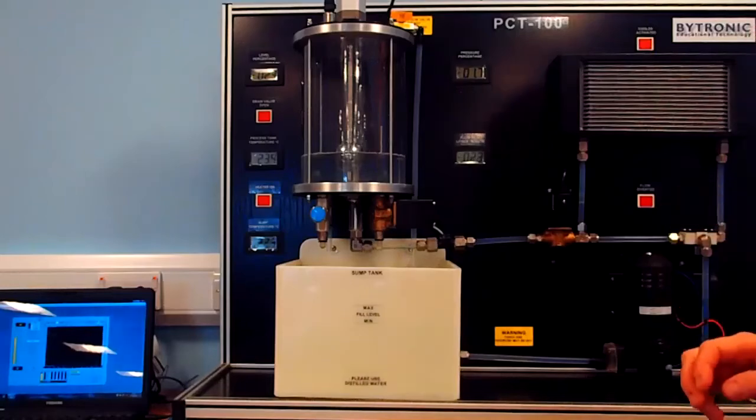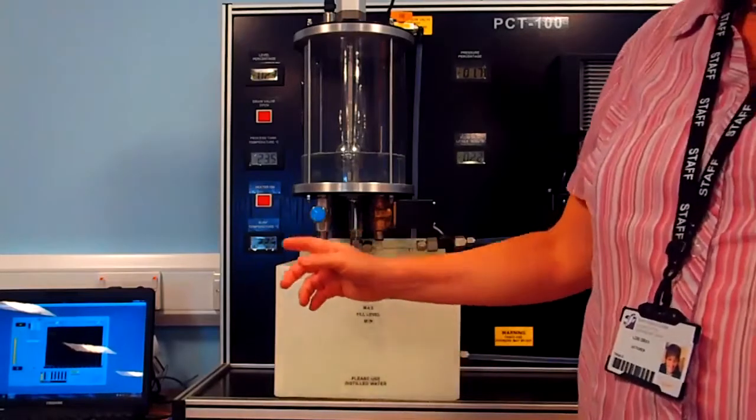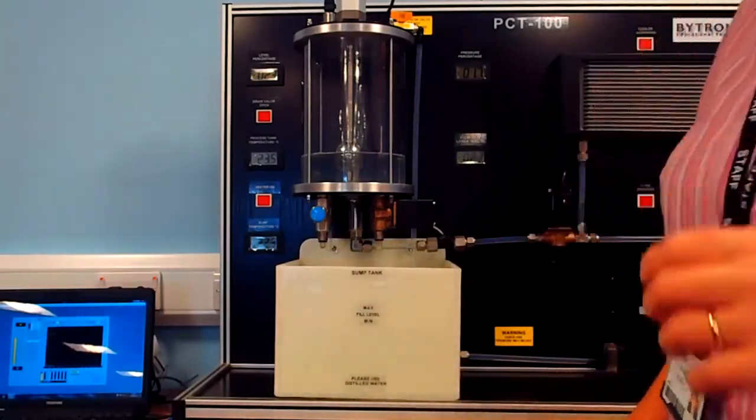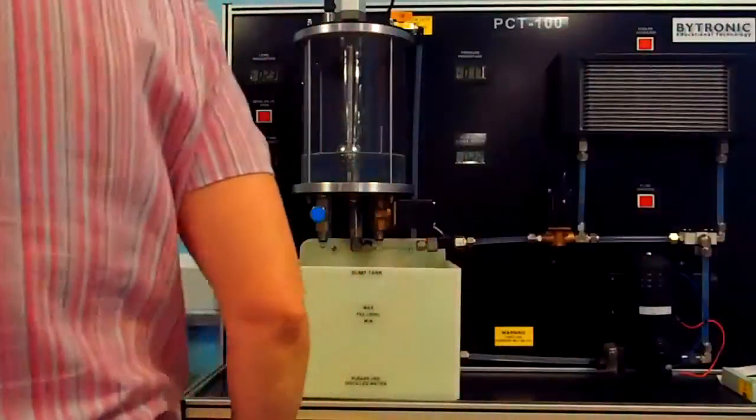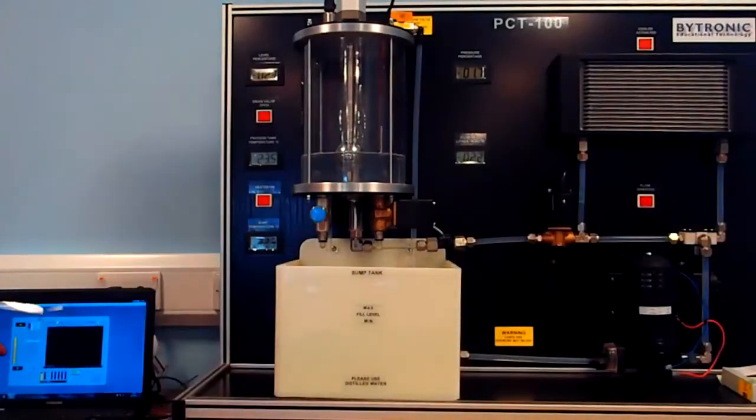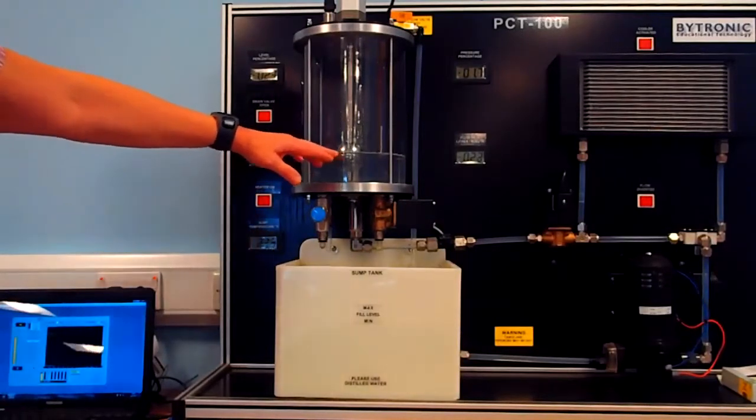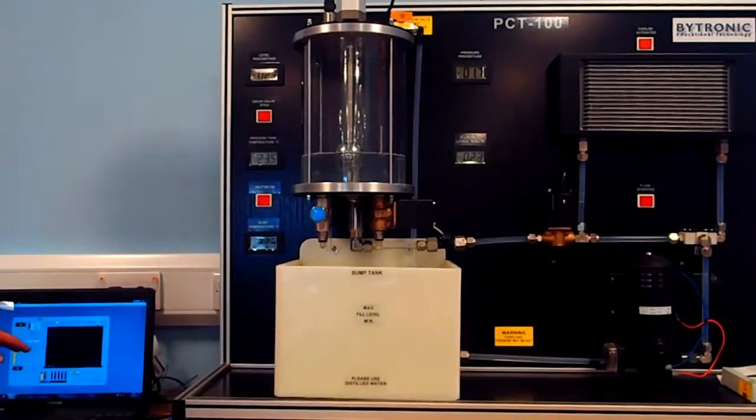So the experiment is we're going to ask for a step change in input using the computer. So down here you won't be able to see it on the film, but we've set a set point of 80. That's 80% of full. And we're starting from a level of 0, which is approximately what the water's at just now. And a step change is a sudden change from 0 to 80% in an infinitely small amount of time. And we're going to watch how the system responds to that.